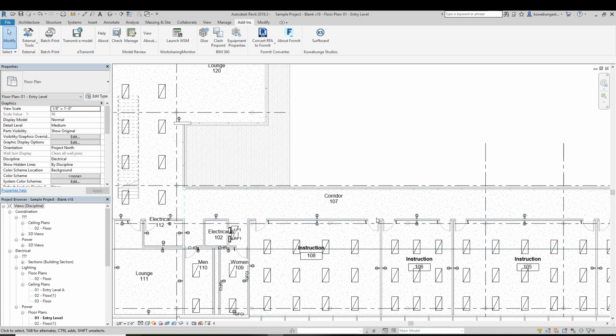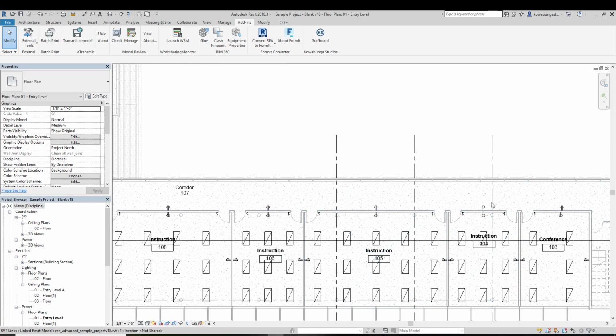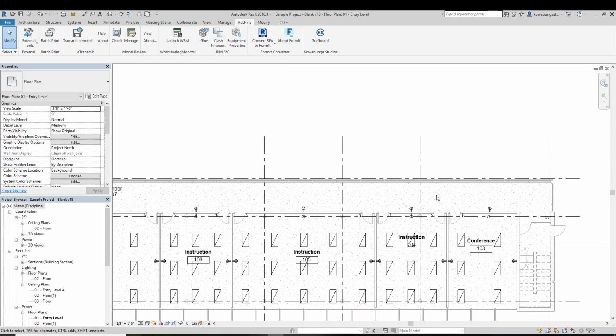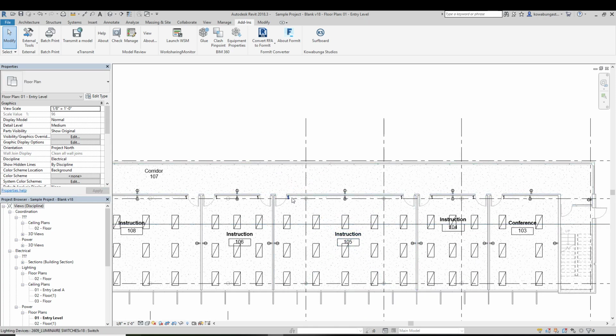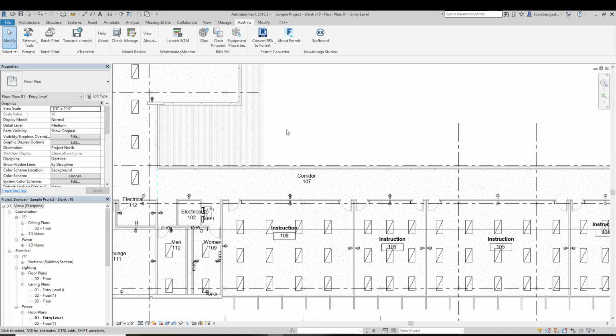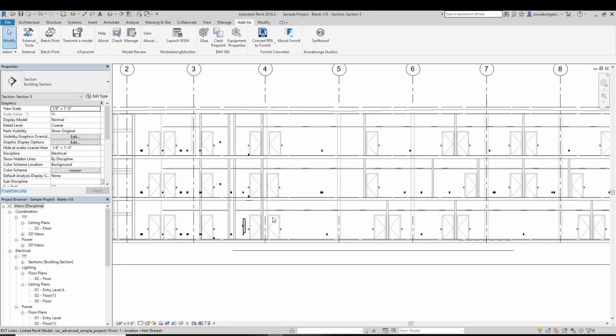This is what I'm talking about, where like a wall intersects. So this is one wall, here's another wall. So in a corridor, it's putting them dead center, which turns out to be pretty close to what you want for convenience receptacles in a hallway. Light switches on the latch side of doors. You can see that throughout. And then if we look at a section here, go to the view, you can see light fixtures, make this fine, are populated into the grid.